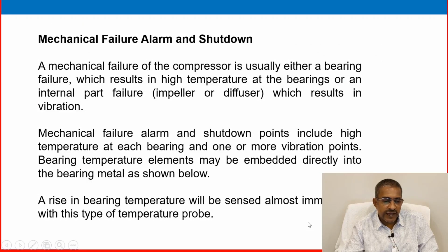Then, mechanical failure, alarm and shutdown. A mechanical failure of the compressor is usually either a bearing failure, which results in high temperature in the bearings, or an internal part failure, impeller or diffuser, which results in vibration. So mechanical failure, alarm and shutdown points include high temperature at each bearing and one or more vibration points.